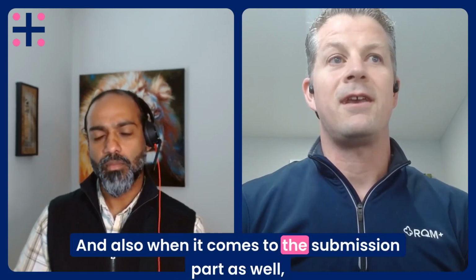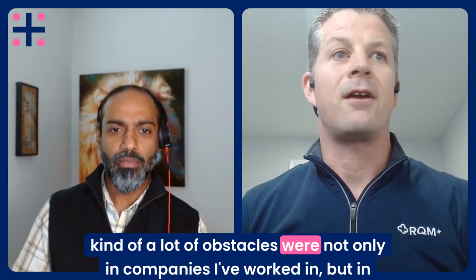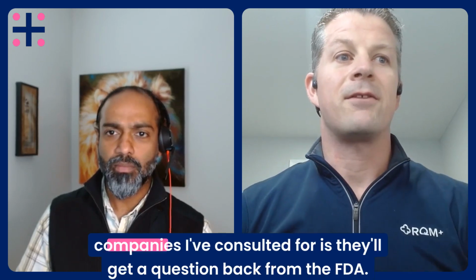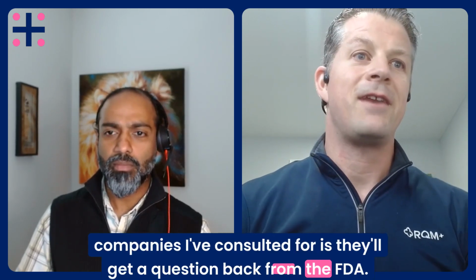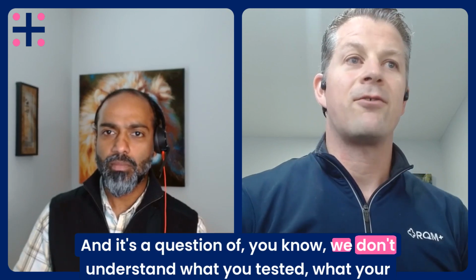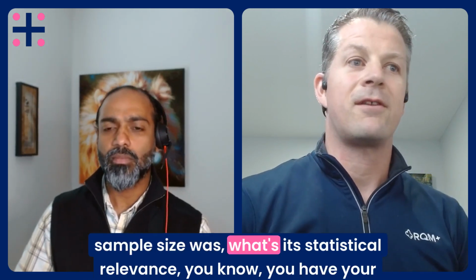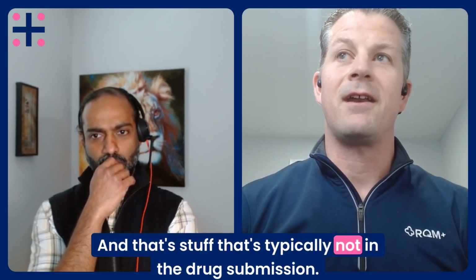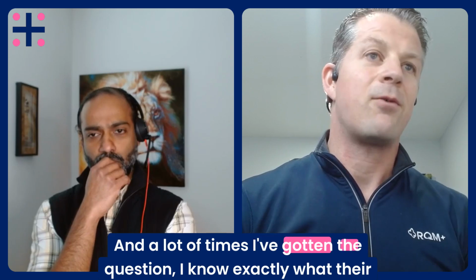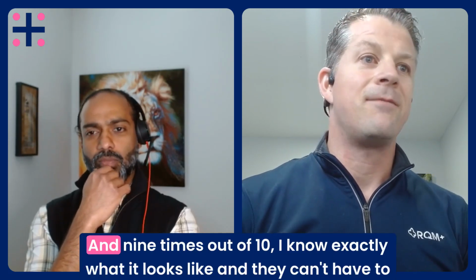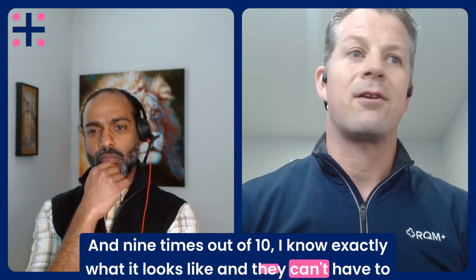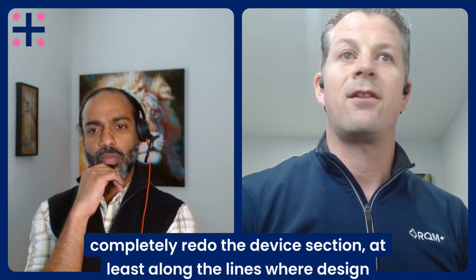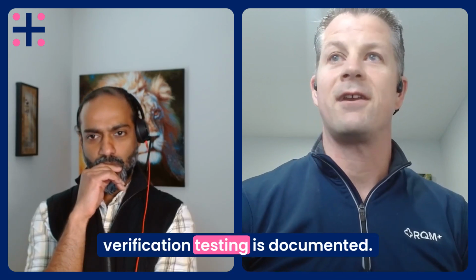And also when it comes to the submission part, there are a lot of obstacles, not only in companies I've worked in, but in companies I've consulted for. You'll get a question back from the FDA saying, we don't understand what you tested, what your sample size was, what its statistical relevance is, what your confidence intervals are. And that's stuff that's typically not in a drug submission. A lot of times I've gotten the question, and I know exactly what their submission looks like. So I'll ask first, what does your submission look like? And 9 times out of 10, I know exactly what it looks like, and they have to completely redo the device section, at least along the lines where design verification testing is documented.